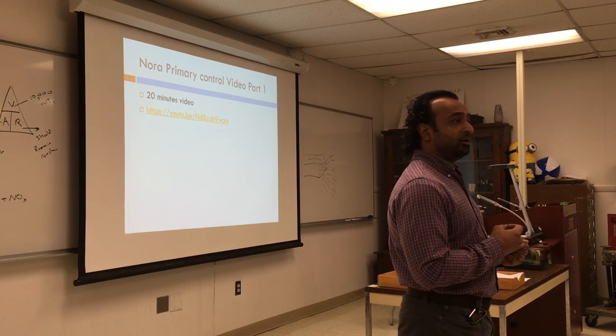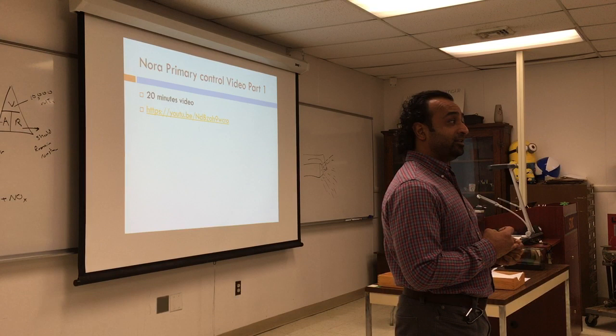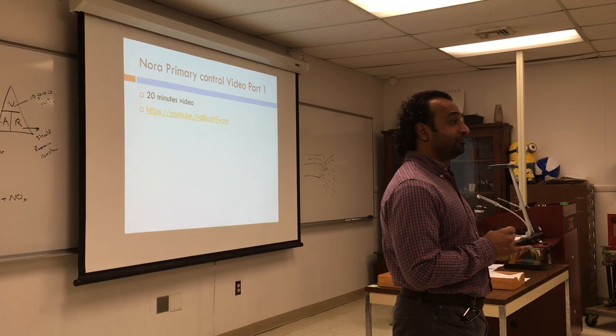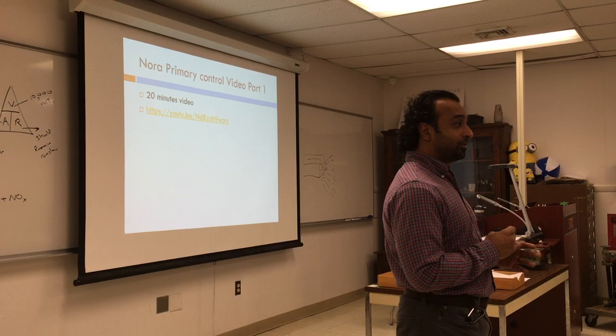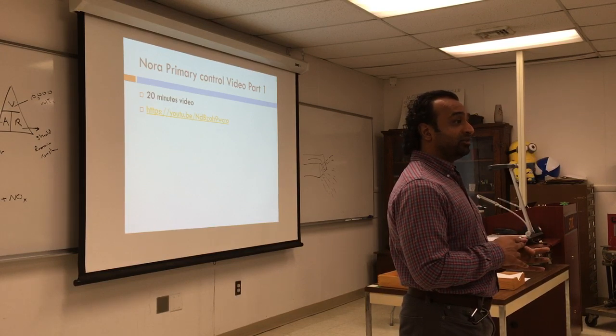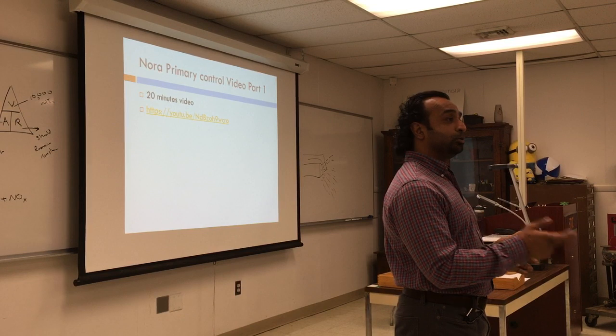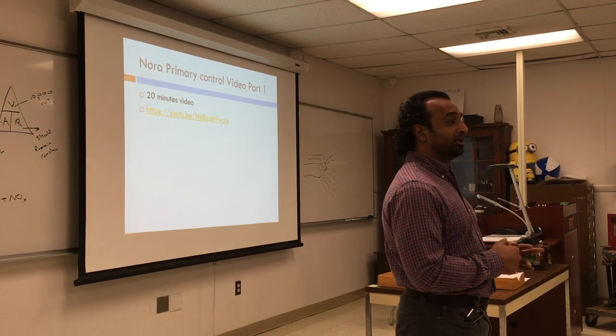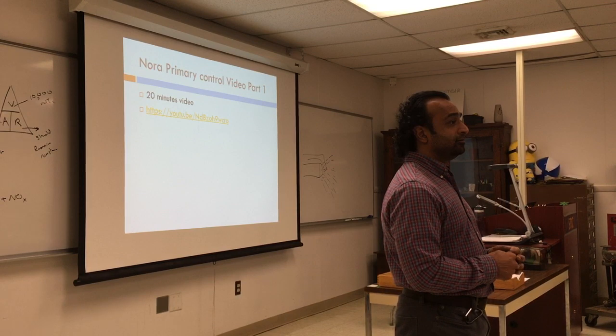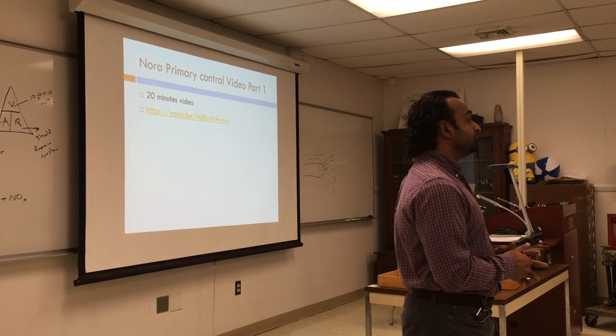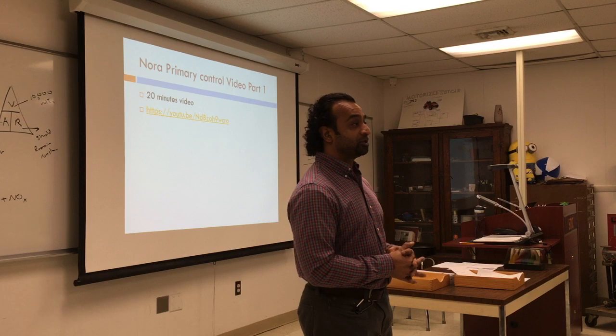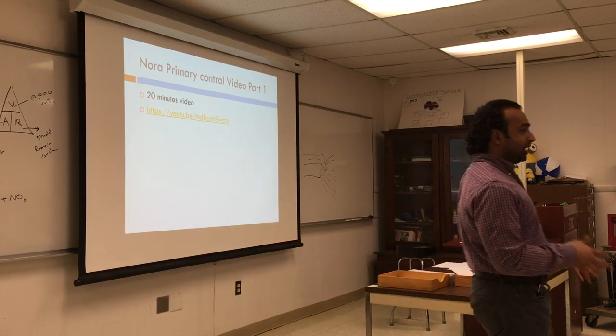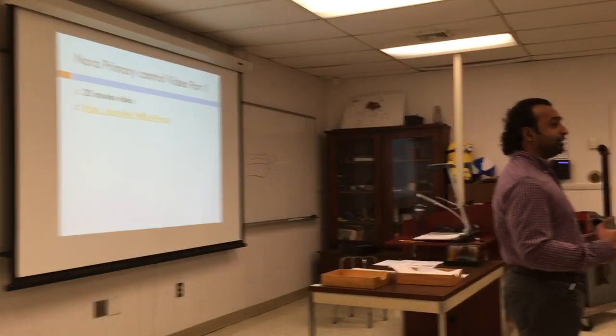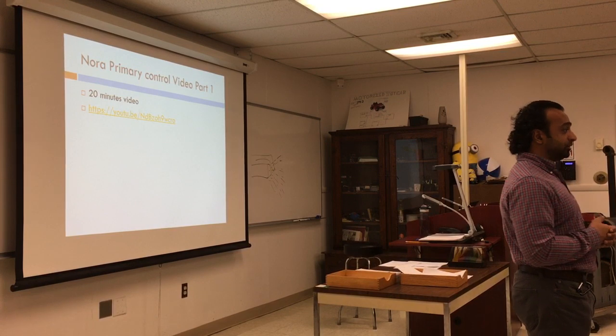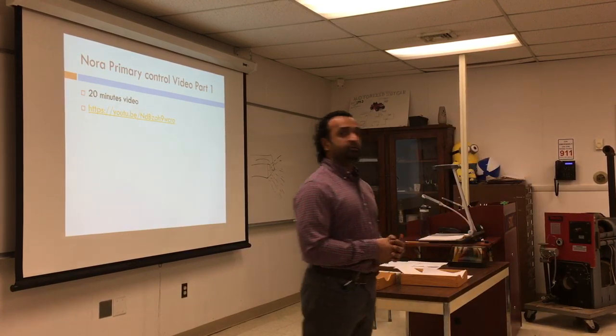We have the motor. The motor controls the fan and the pump, right? We have an oil valve. The oil valve permits the oil to go through the pump onto the nozzle. We have ignition, and ignition will go out. And we have our cad cell that will verify the flame. All types of primary control do the same function. What is the safety timing on now? Just to prove light? 15 seconds. Any more than that, and I think it's a waste because you're going to pump oil into the chamber. It's unsafe. Okay, that's all.